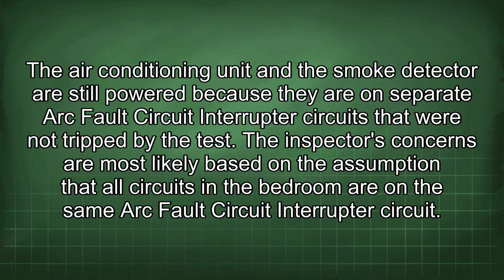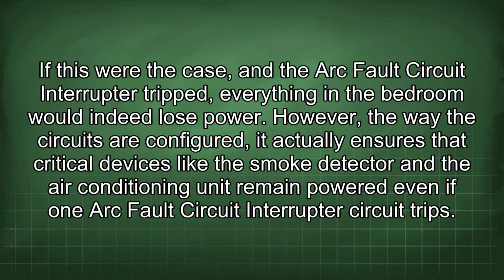The inspector's concerns are most likely based on the assumption that all circuits in the bedroom are on the same arc fault circuit interrupter circuit. If this were the case, and the arc fault circuit interrupter tripped, everything in the bedroom would indeed lose power. However, the way the circuits are configured, it actually ensures that critical devices like the smoke detector and the air conditioning unit remain powered even if one arc fault circuit interrupter circuit trips.